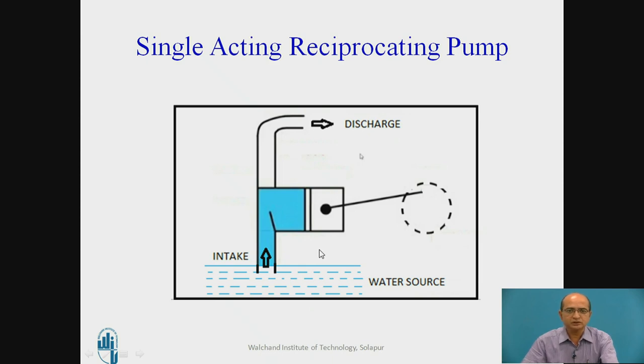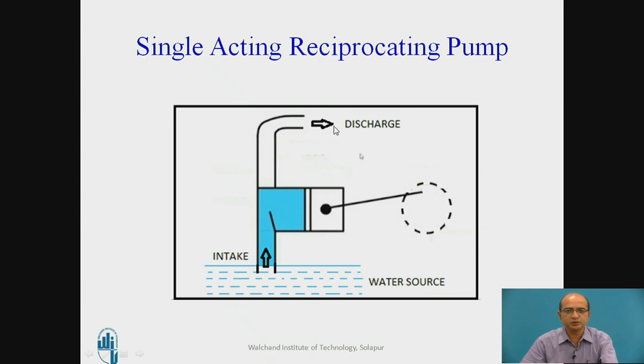But in this case, the principle is very simple. When the piston moves in the outward direction, there will be creation of vacuum, and due to that vacuum, the water from the sump or the storage tank rushes inside the cylinder. When the piston moves from the outer dead center towards the inner dead center, the inlet valve closes and the delivery valve opens, and the water rushes to the delivery pipe.